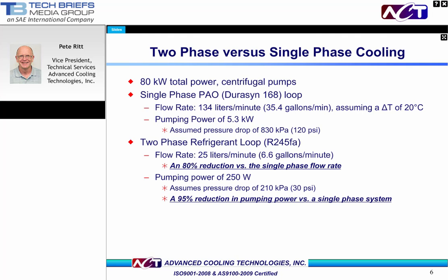To give a clearer sense of the flow rate and pumping power differences between pump liquid and pump two-phase systems, the following comparison is provided for an avionics application. In order to dissipate 80 kilowatts of heat, a pumped liquid system using PAO as the working fluid would require a flow rate of 35 gallons per minute and approximately 5.3 kilowatts of power. A pump two-phase system using R245FA would require only 6 gallons a minute and 250 watts of power, which is an 80% reduction in flow rate requirements and a 95% reduction in power requirements compared to a pump liquid system. A significant difference for sure.